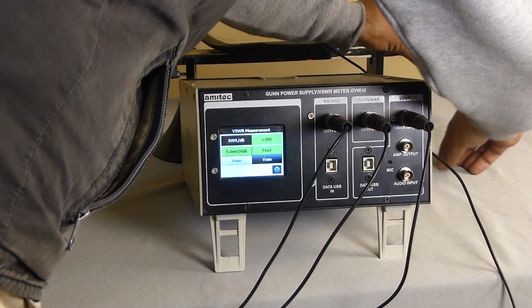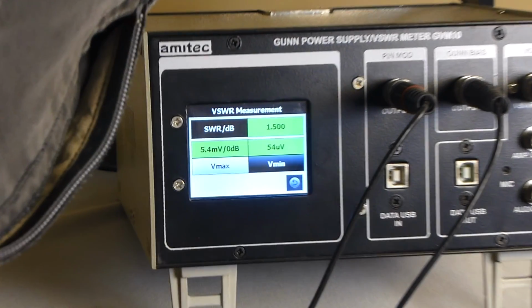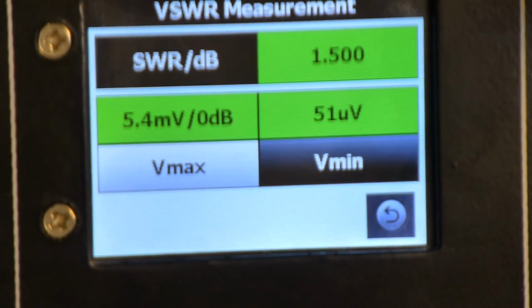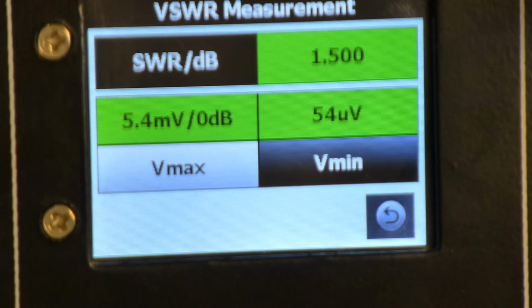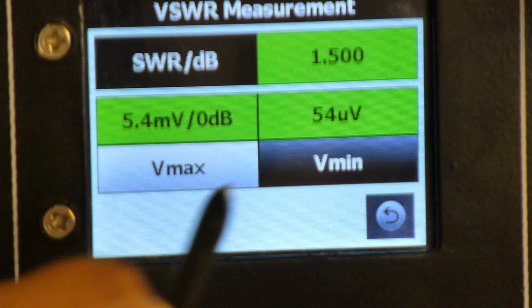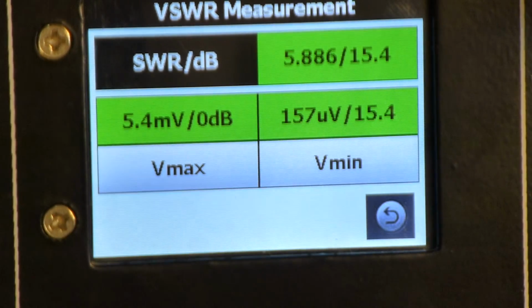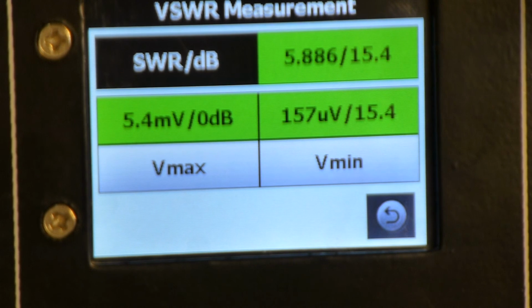Make sure while doing the actual measurements, all the bolts and nuts have to be tightened properly, otherwise there will be an impedance mismatch and the readings will be erroneous. Now with the termination connected instead of the shorting plate, we will measure Vmin. So right now it is giving a directivity of around 15 dB, but it is much more than 15 dB.